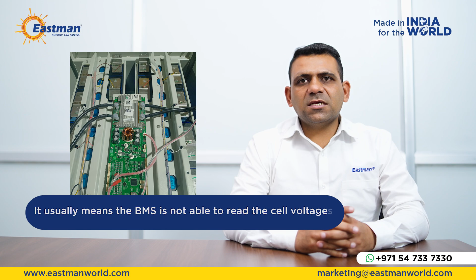AFE chip's job is to monitor each cell voltage and temperature. So if it loses communication, it throws an error for safety. First, start with the physical check. Many times the problem is simply loose or damaged connections.